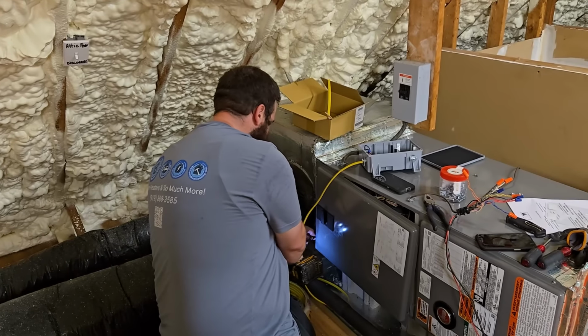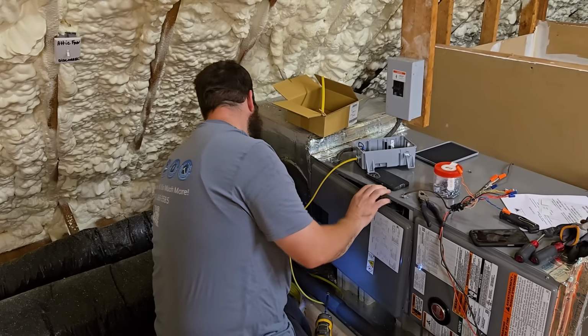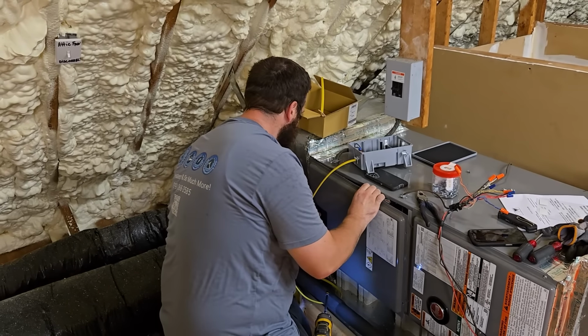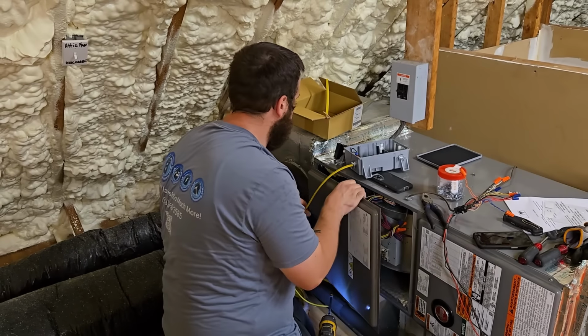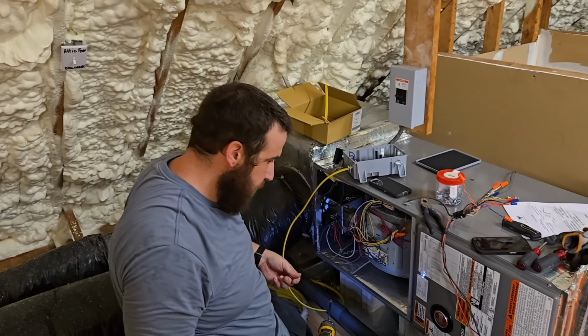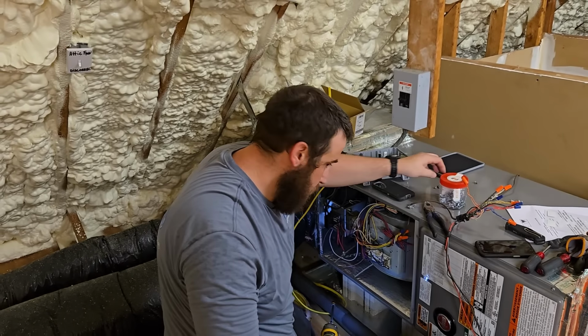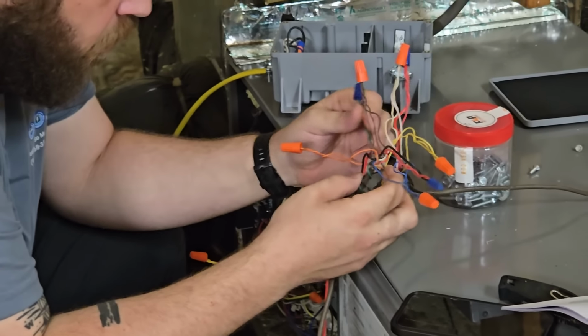In order to use a smaller generator unit, we need to use what we call load shedding devices. These get installed on the large electrical loads in your home, typically your heating and air equipment. They allow the generator to get to full power before allowing these loads to turn on, stopping the generator from overloading, usually with a delay of a few minutes.